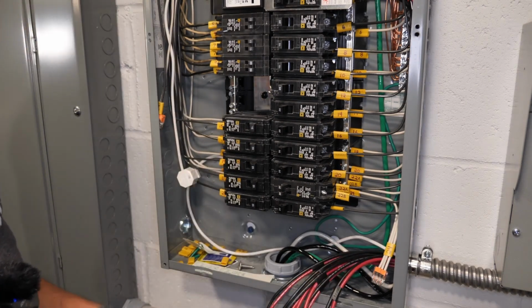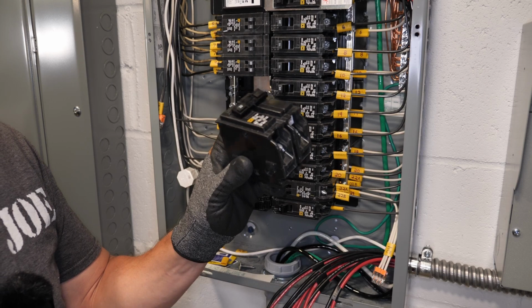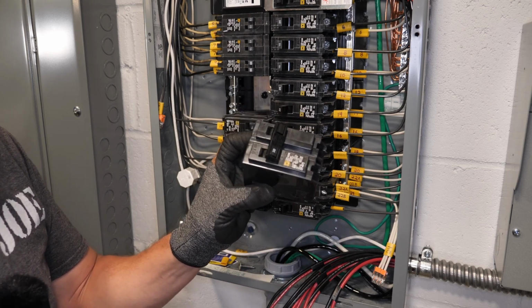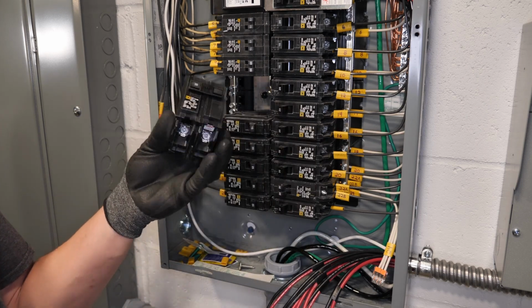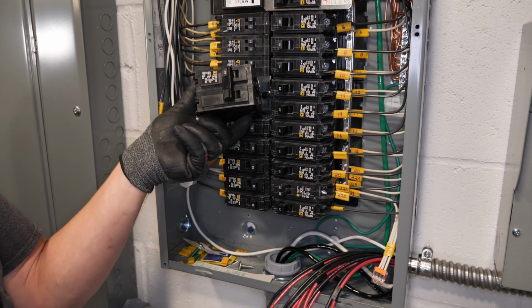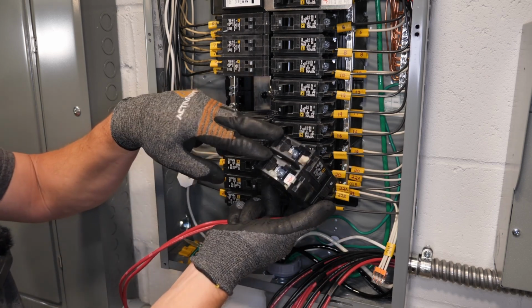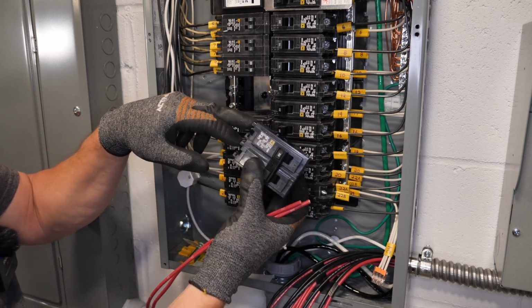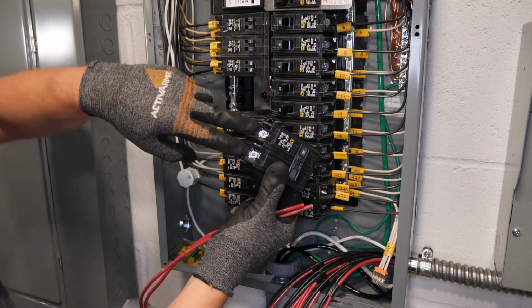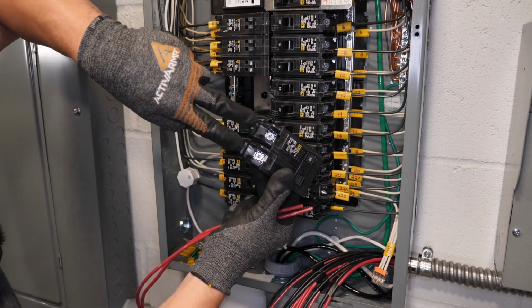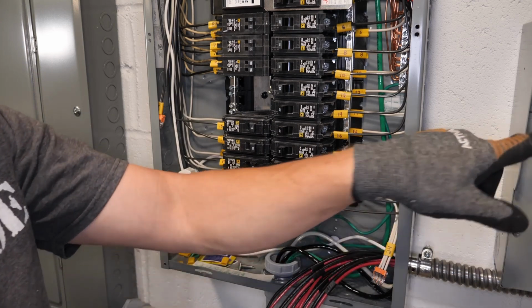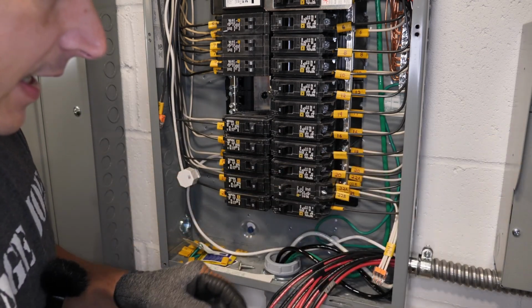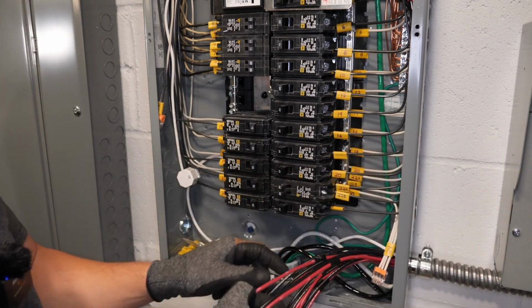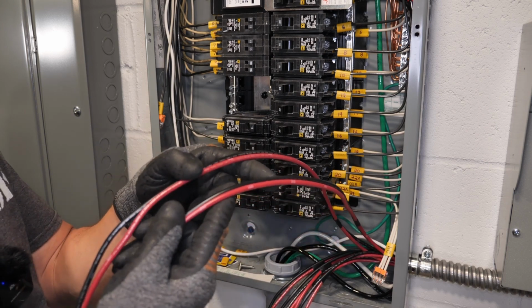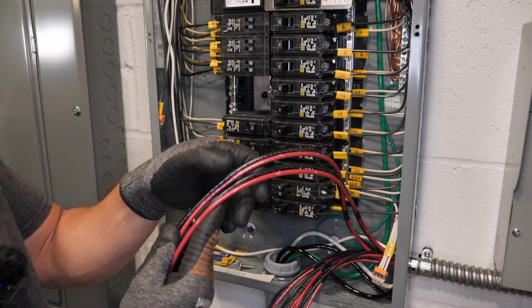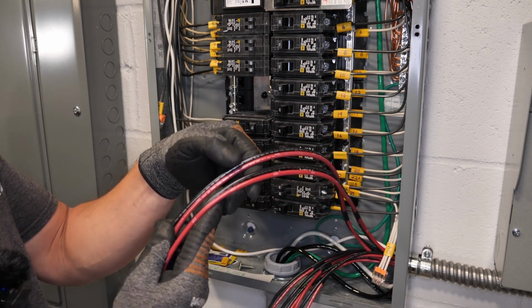Now I'm going to give you a quick example of how to wire the 240 volt circuit breaker. Just imagine this is already installed and you have, let's say, a well pump installed. Basically what we're going to do is remove the well pump from here. Over here on the panel, you've got circuit A and B, so you're going to find A and B on the wiring. Right here we have A, right here we have B.